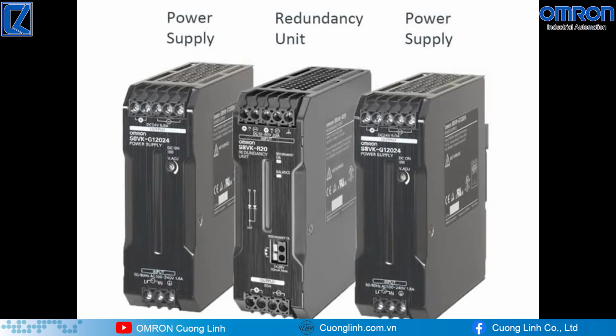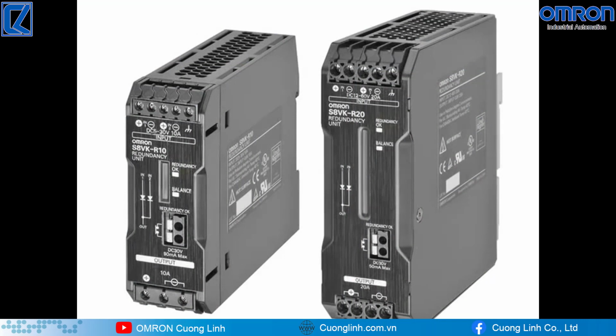The redundancy unit is designed to properly balance the output load between the two power supplies, effectively using each power supply. The power supplies are correctly sized. This will extend the life of the power supplies by drawing half the load from each power supply. The redundant unit is also in place to properly transfer the complete load to one or the other power supply if one should fail. The OMRON redundancy units have a redundant monitor system that includes a redundancy operating LED, a voltage balance LED, and a signal output for failure of a power supply.